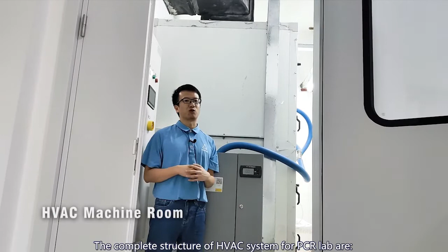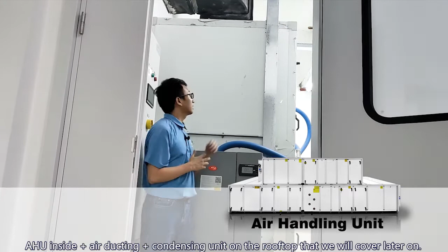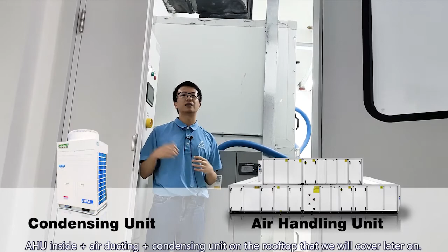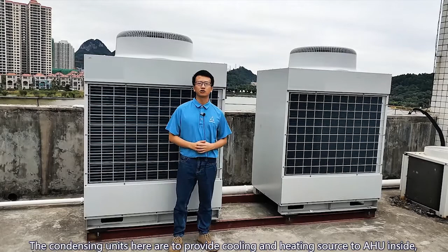The complete structure of the HVAC system for the PCR lab is the AHU here inside, plus the air ductings and another condensing unit on the rooftop that we will cover later on. The condensing units here provide cooling and heating source to the AHU inside. The fresh air is treated by filtering, heating and cooling, and then sent through the air ductings all the way down to the PCR lab. In a word, the HVAC system is to maintain the PCR lab temperature and humidity at a constant level.